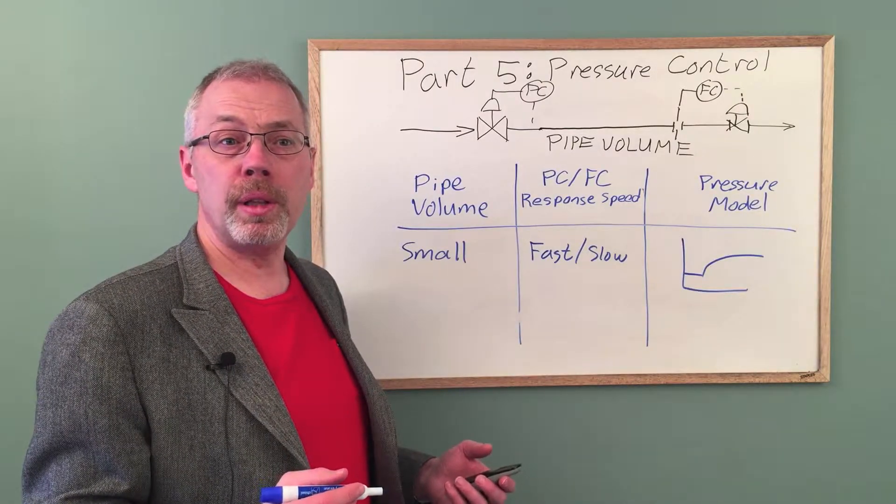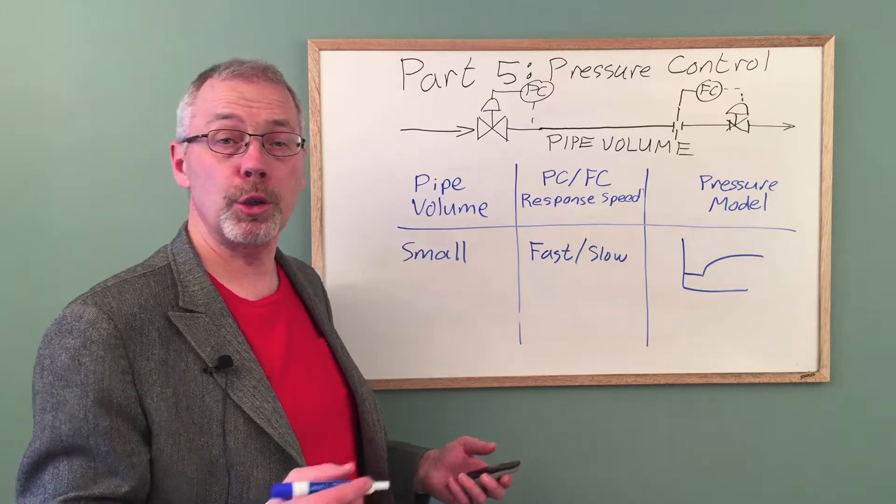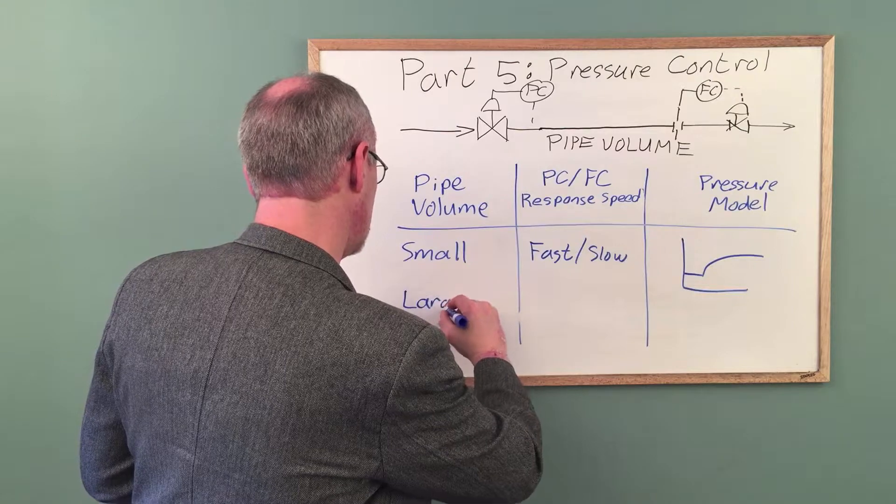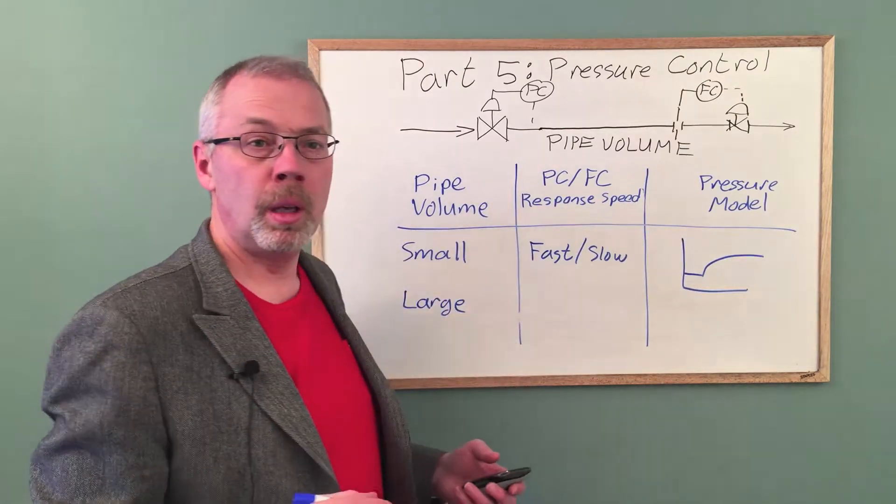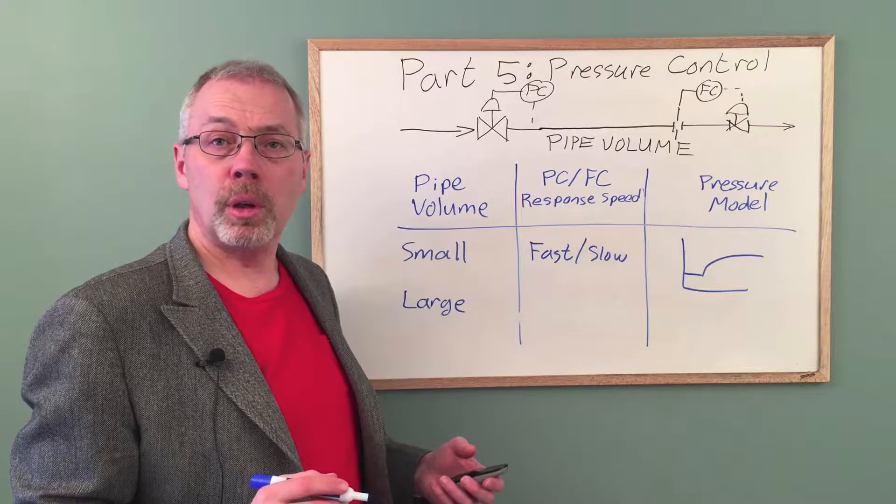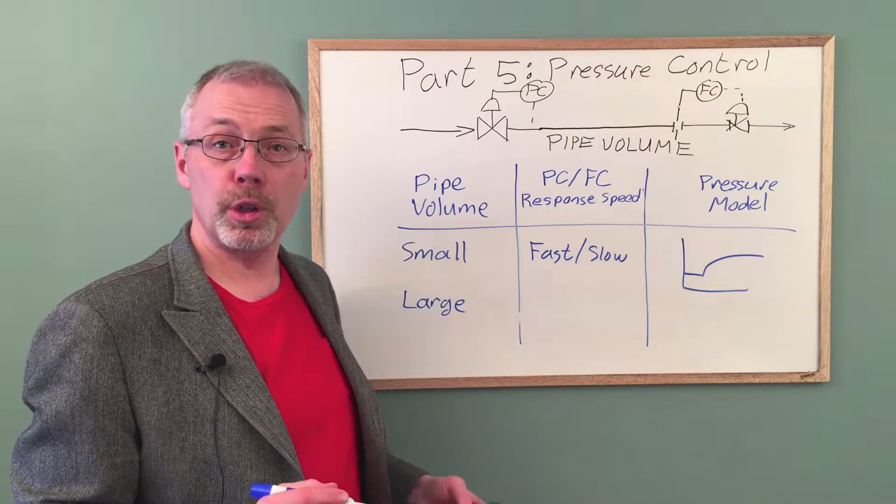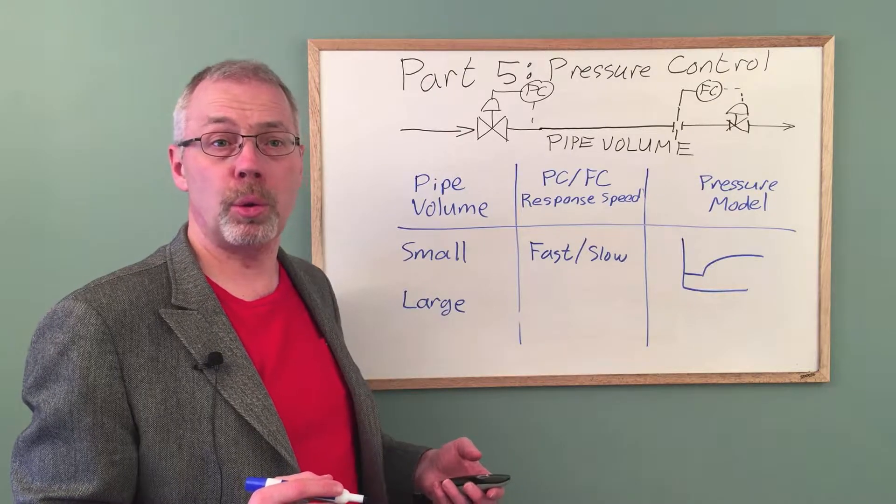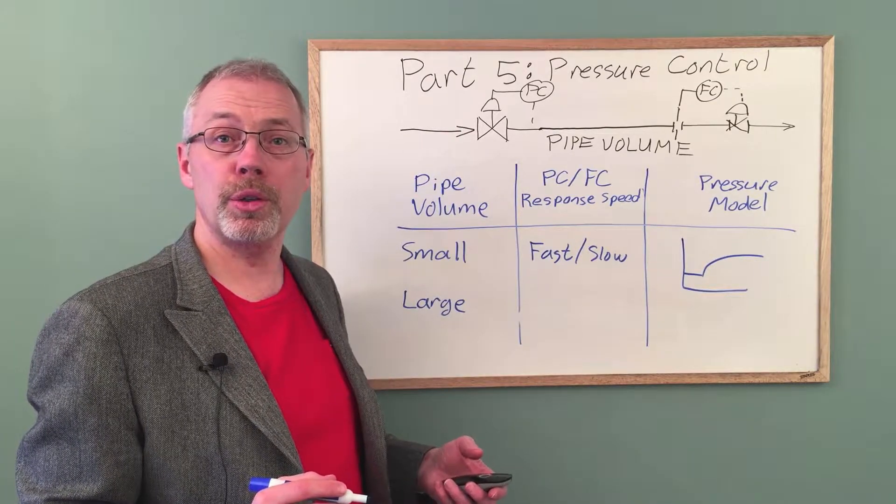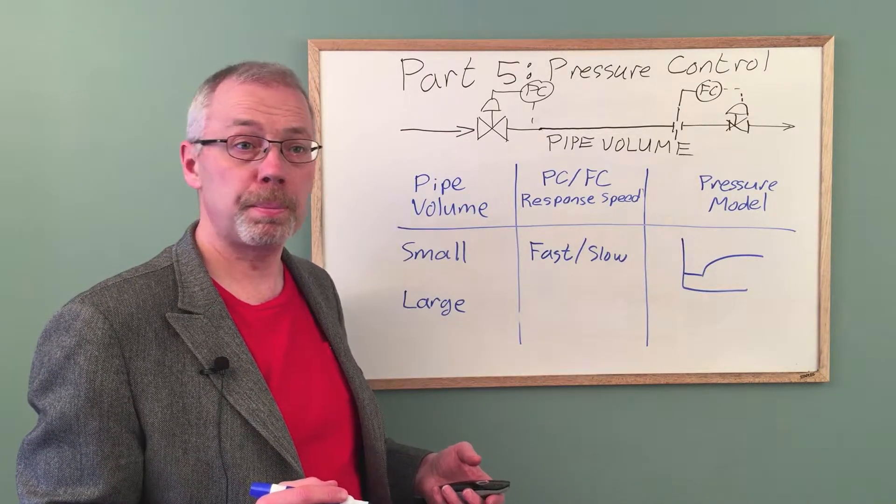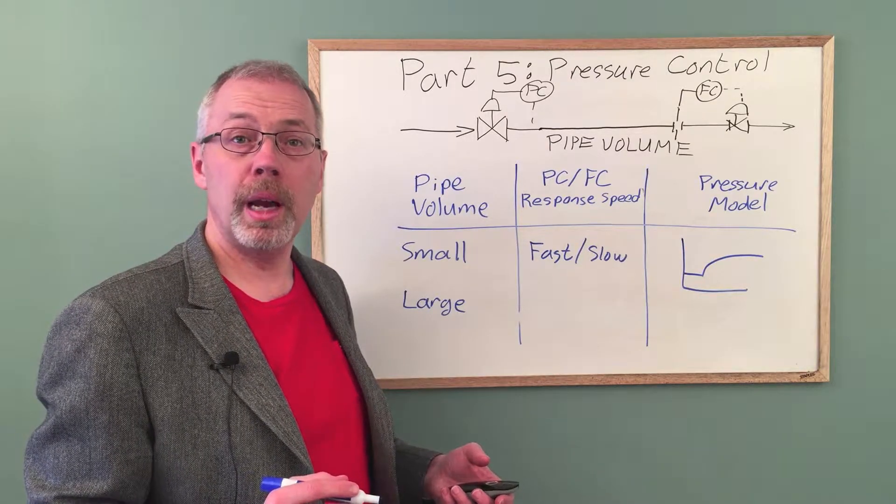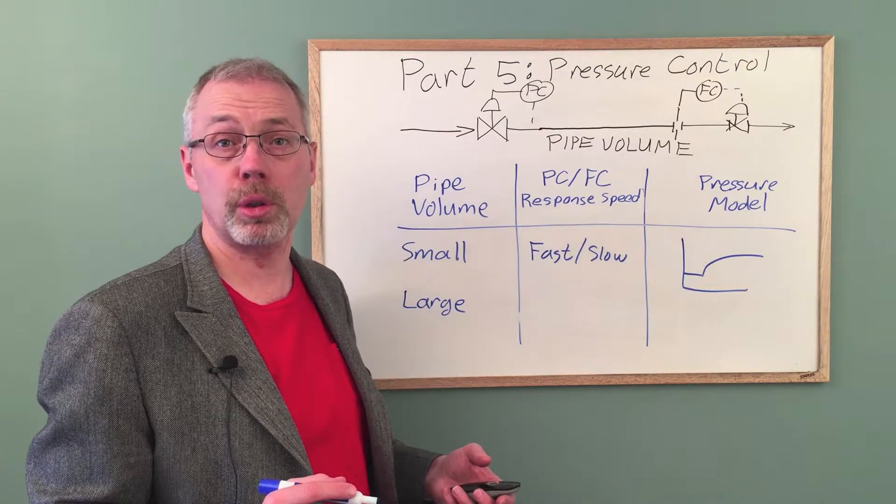Now let's consider the case where the pipe volume is quite large. This is still an interacting system but the large pipe volume provides some surge capacity. In this case, the flow controller is more important to ensure steady firing of the equipment. Flow must be tuned to respond quickly and the pressure controller will be tuned to respond somewhat slower.